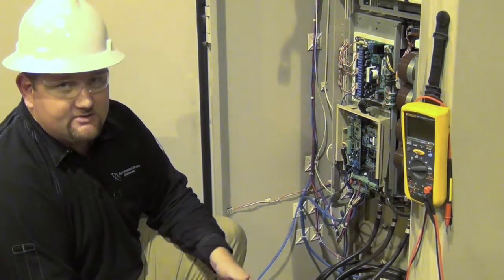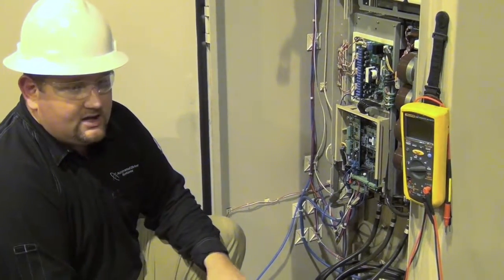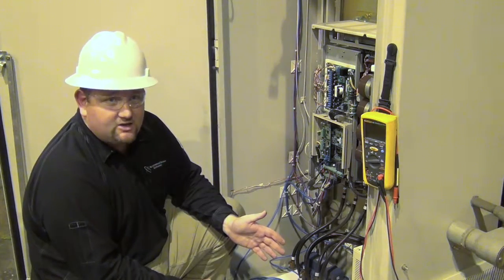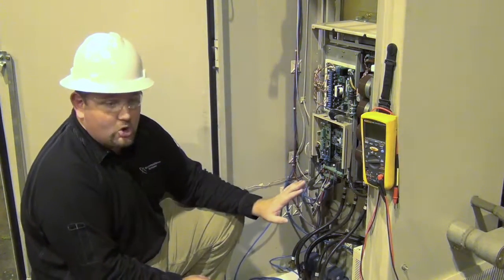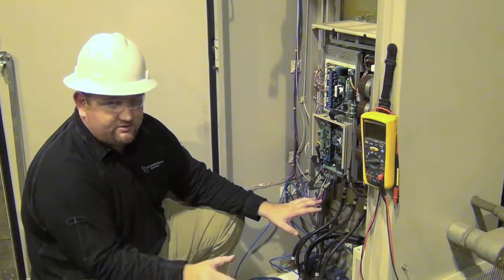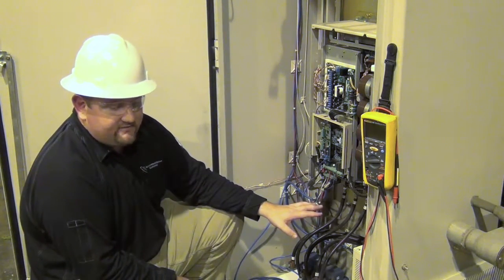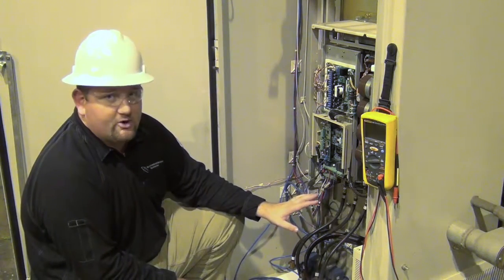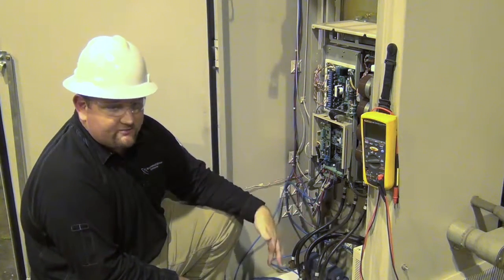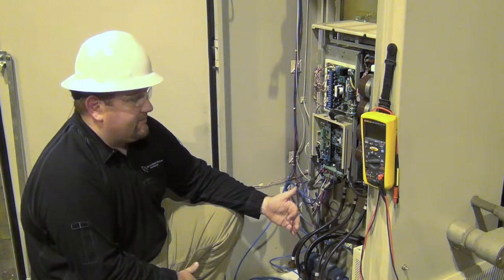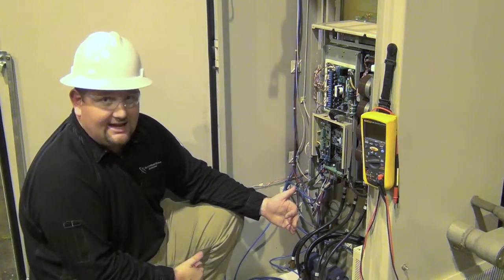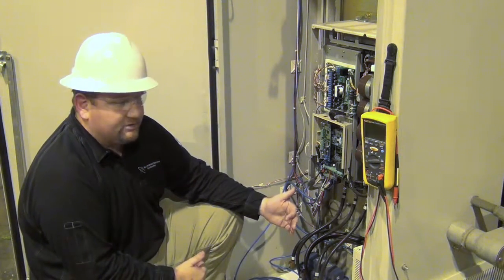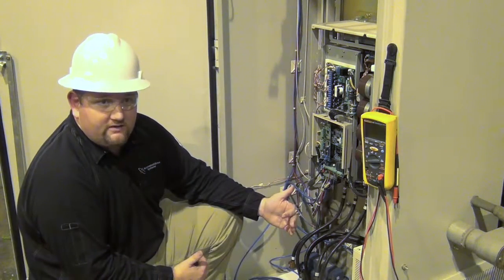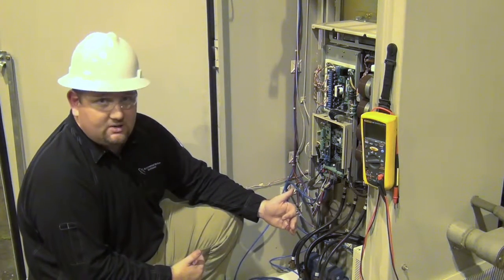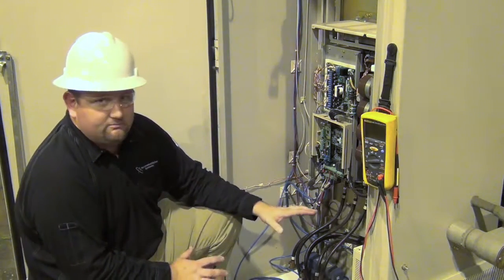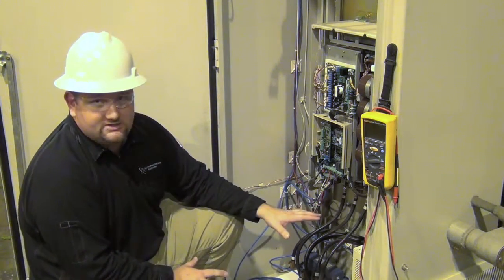A couple keynotes, as far as using a vacuum cleaner, we always recommend that you use an ESD safe vacuum cleaner, especially if you're going to vacuum anywhere on any of the boards. So the one we use is a 3M brand, and it is an ESD safe vacuum cleaner. And then as far as using compressed air, you always start at the top of the drive, work your way down, dust falls, and you don't want to be using 100 psi plus plant air. If you're going to use an air compressor to blow a drive out, ideally you'd want to be 40, 50 psi, for sure 60 psi is an absolute max. We're trying to blow the loose dust off, we're not trying to blow components out of the drive.